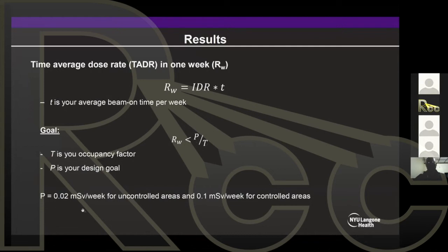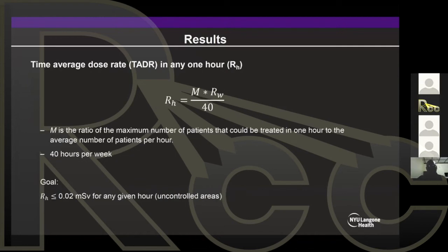And remember, your design goals are set at 0.02 millisievert per week for uncontrolled area, 0.1 millisievert per week for controlled. The third number you're going to look at is the time average dose rate in any 1 hour. So let's say you did your calculations assuming a number of patients per week, with an average number of patients per hour. What you're going to do to get this number, you're going to divide that RW that was per week by 40, assuming 40 working hours per week. And then you're going to multiply by this factor. M is the ratio of the maximum number of patients that could be treated in 1 hour to the average number of patients per hour, right?